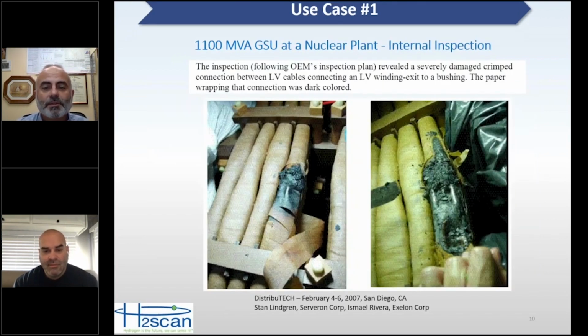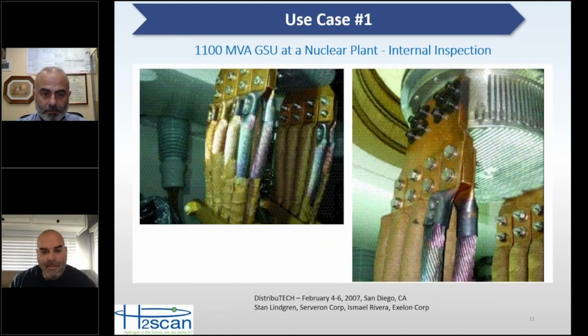When they did an internal inspection, they found this was the low voltage leads coming out of the winding going up to the low voltage bushings. They found some overheated crimp connections, and they actually found 2 problems. If we look at the next slide, we see when they peeled the paper off at the end of the leads, and somewhere around 20,000 amps is the normal rating on the low side of this transformer. So it, of course, was carrying a lot of current. There are 16 of those conductors connected to one bushing. To me, it's either 500 or 750 copper. So a very large amount of current.